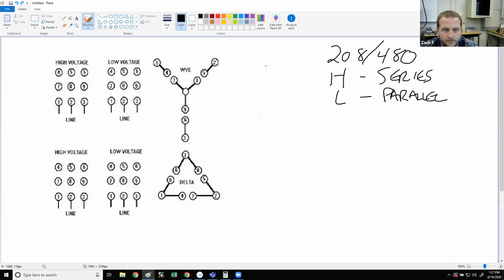Series or parallel? Series. Series for high. So all we're going to do is join these windings right here, these windings right here, and these windings right here, right? Yep. So Y high, it looks like this. 4 to 7, 5 to 8, 6 to 9.